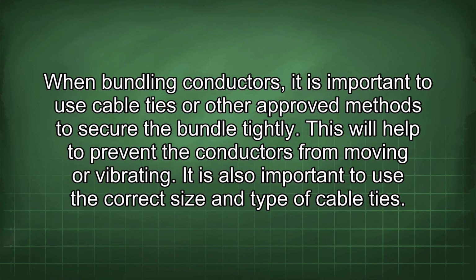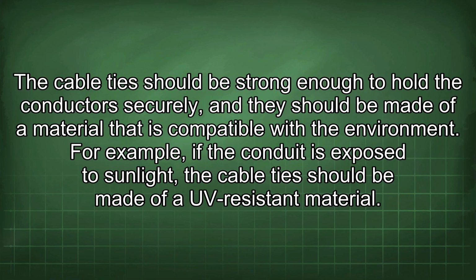When bundling conductors, it is important to use cable ties or other approved methods to secure the bundle tightly. This will help to prevent the conductors from moving or vibrating. It is also important to use the correct size and type of cable ties. The cable ties should be strong enough to hold the conductors securely, and they should be made of a material that is compatible with the environment. For example, if the conduit is exposed to sunlight, the cable ties should be made of a UV-resistant material.